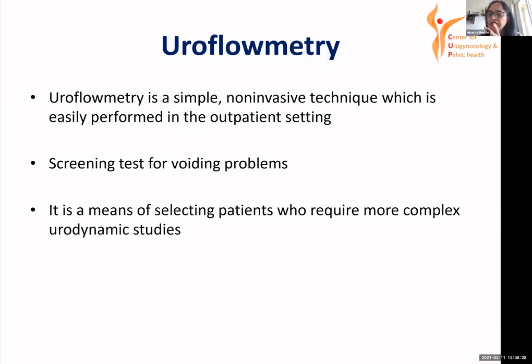You see this on the left, there's a weighted disc, meaning this jar is sitting on a weighted disc. It is measuring the weight. As the jar is filling up, as a woman is peeing, it's giving you a calculation of volume and of flow rate. So it's a weighted disc. There's another kind of uroflowmetry where it's a rotating disc, right? There's an element in this that rotates. As you pee, the rate of rotation changes, and as the rate of rotation changes, you're getting the flow volume and the flow rate. These are the two basic kinds of flow recorders that you will get in your clinic, right?